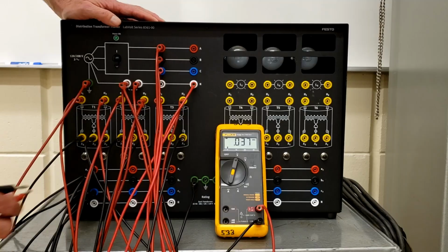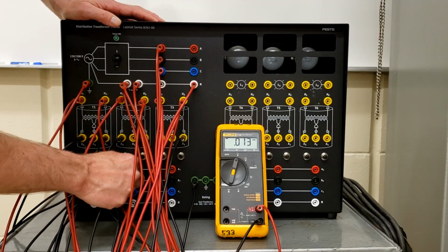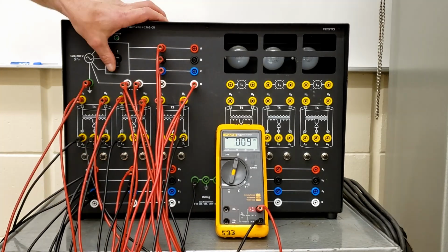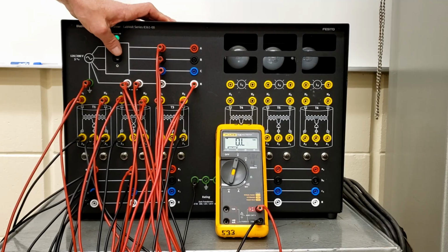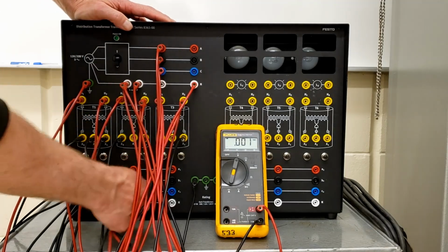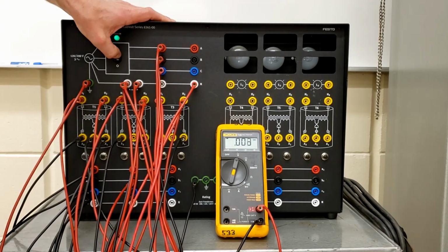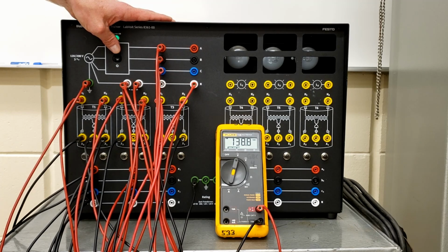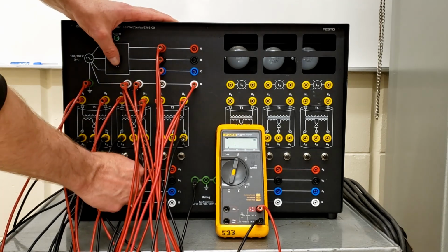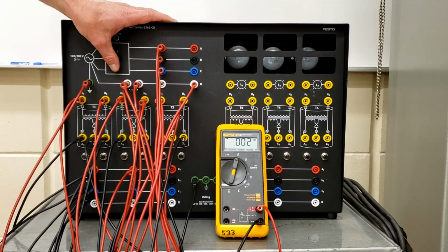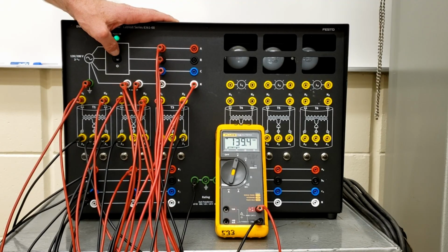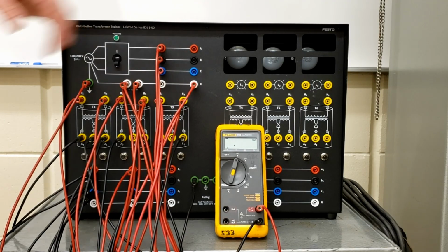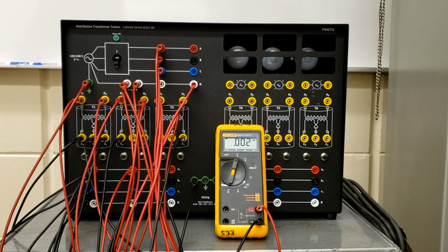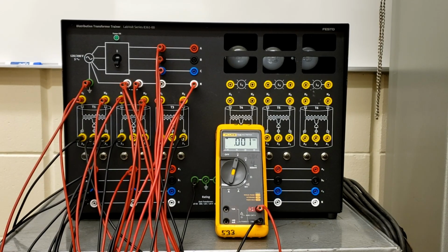So let's check our voltages from A1 to B1 now. So should be 140. Excellent, 138.9. Okay, we'll look at from B to C, should be identical. 140, and then from C to A should be identical at 140. Excellent. Okay, so those are our voltages from A1 to B1, B1 to C1, C1 to A1.